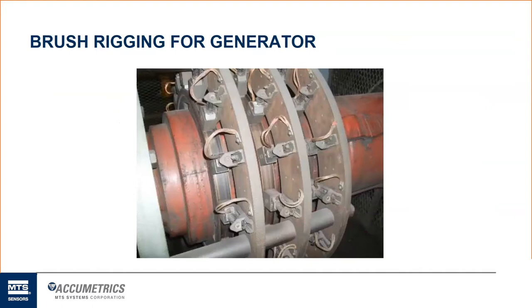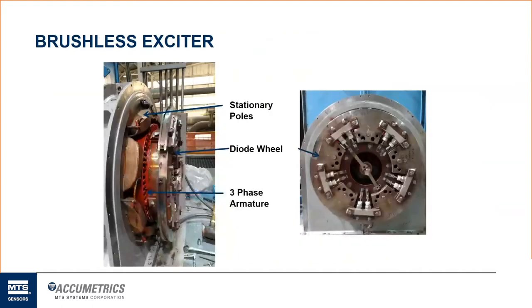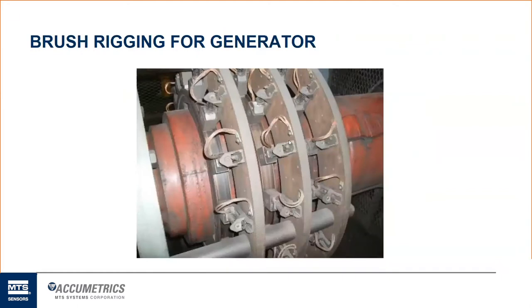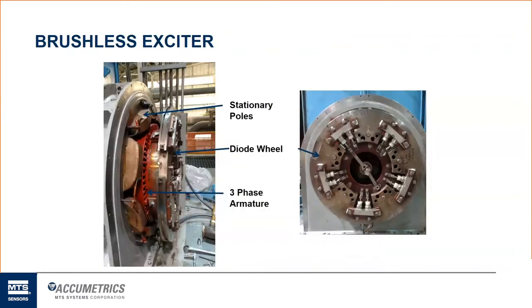In contrast to the brushed systems, they have what's called a brushless exciter. You can think of a brushless exciter basically as an inside out generator. So they have the three phase AC windings, and all of the armature and electronic circuitry that is required to produce the DC field out on the rotor itself. As a result, you basically get three phase AC currents on the rotor. They have to be rectified using silicon diode rectifiers to produce that DC current source that then powers the generator itself.